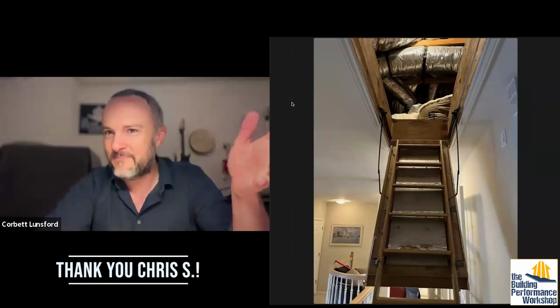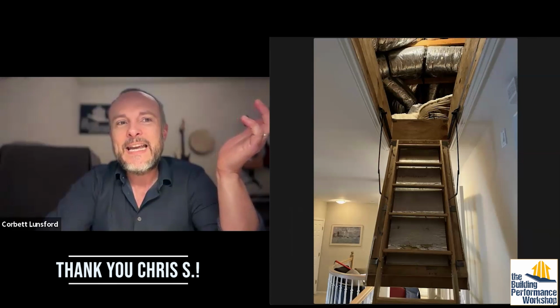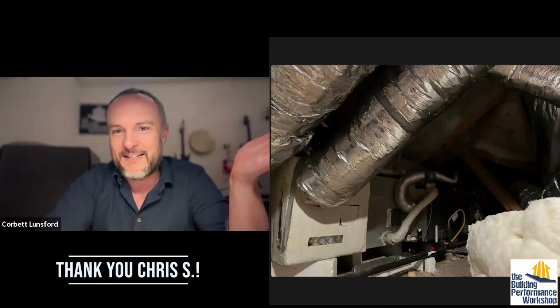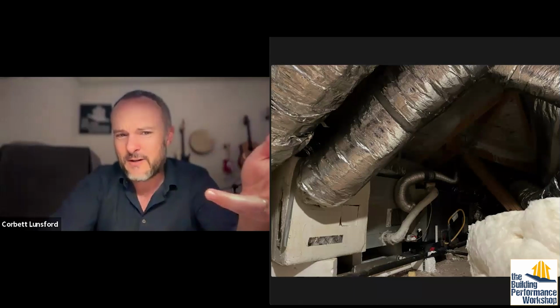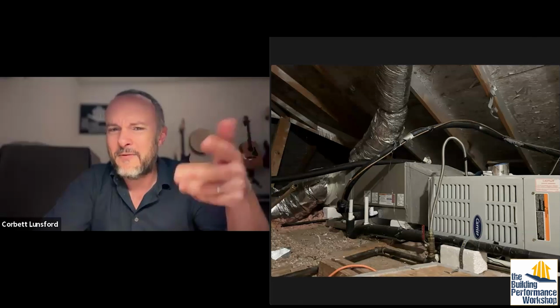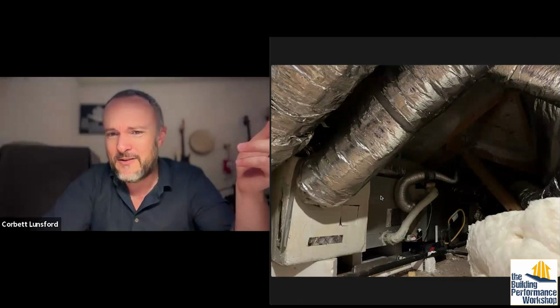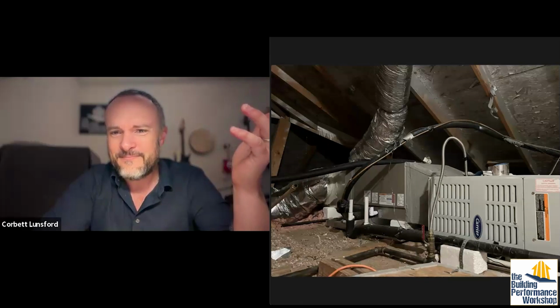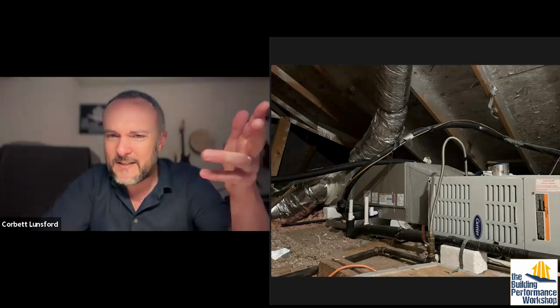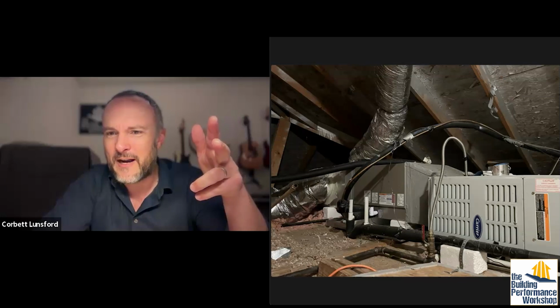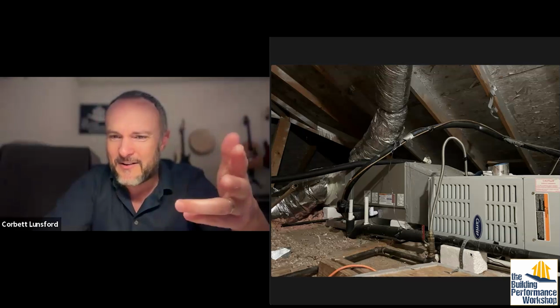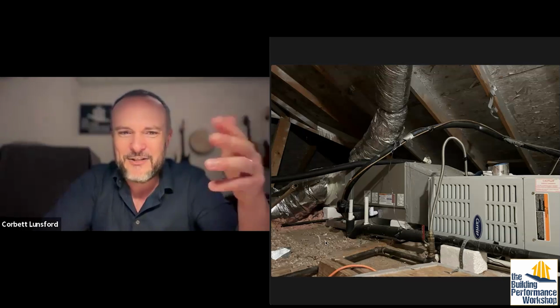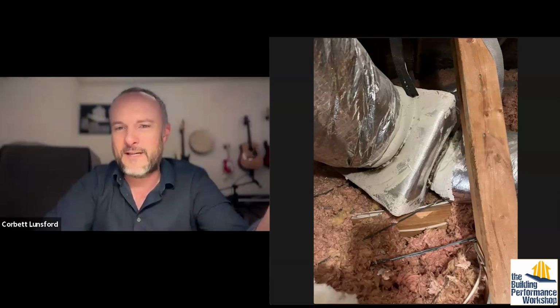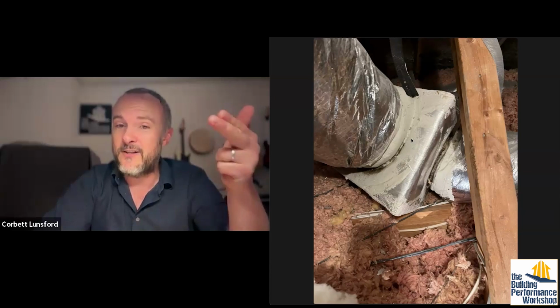So these are some photos from a client of mine who had this system. And when you step up into an attic like this, it can be, like I said, make you a little bit sad. So looking at this kind of thing, being like, okay, is this okay? It kind of looks like maybe it's not okay. We've got this flex dryer duct being used as the flue. Yeah, that's definitely not okay. Yeah, it looks like duct board that's then painted with mastic. We have an atmospheric draft furnace. We've got duct supplies just sitting out and around. We have dirty insulation. This kind of attic just makes it so confusing. It's like having a messy room. It's like, where do I start? Yeah. So we've got mold showing up on the collars here.